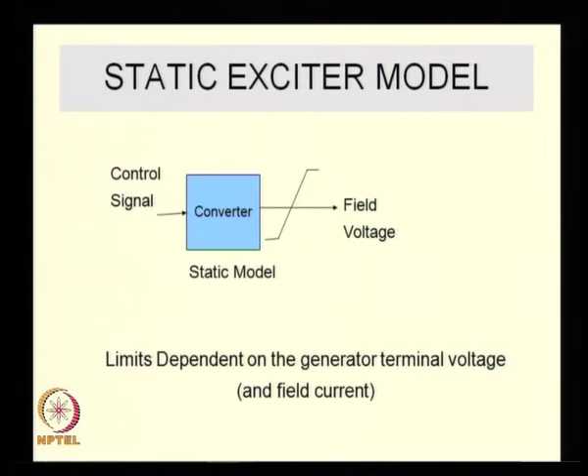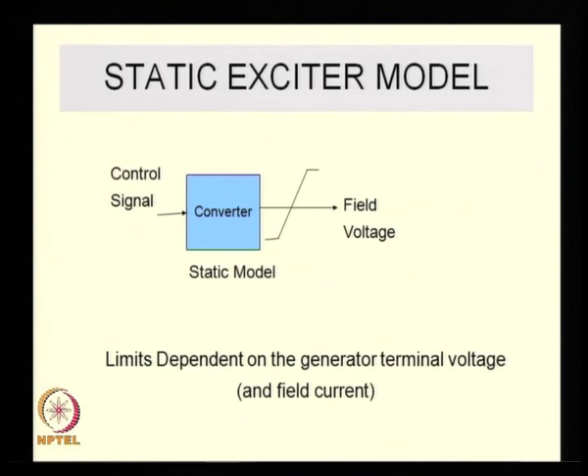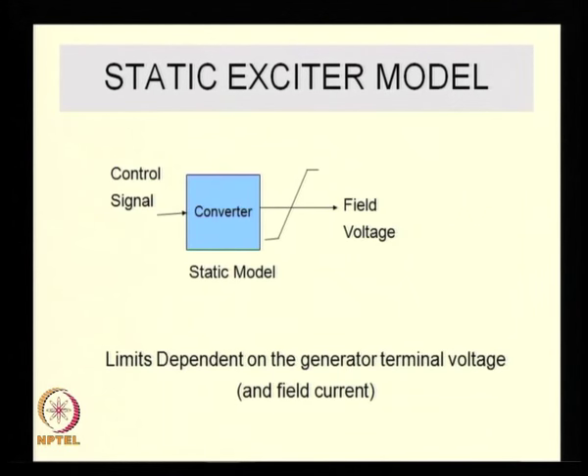To summarize the static excitation model: the control signal goes into the converter, which can be modeled as a static block. The field voltage is algebraically related to the control signal — there are no differential equations or delay elements. The simplest model is a simple algebraic relationship between the control signal and the field voltage.